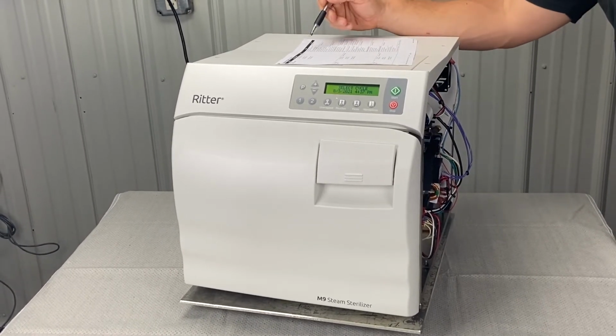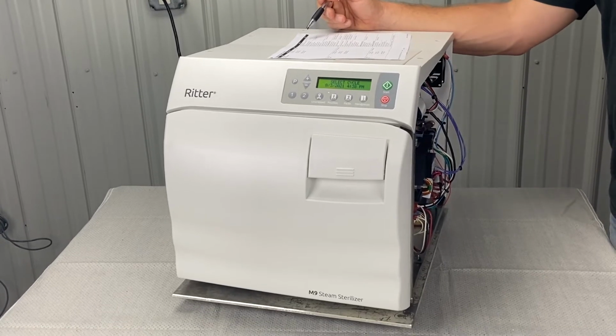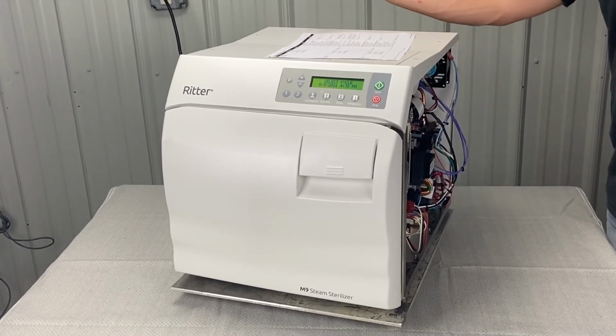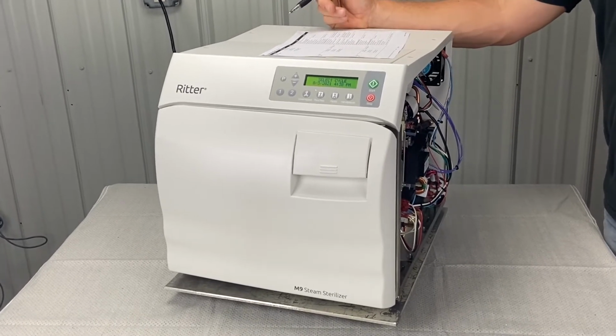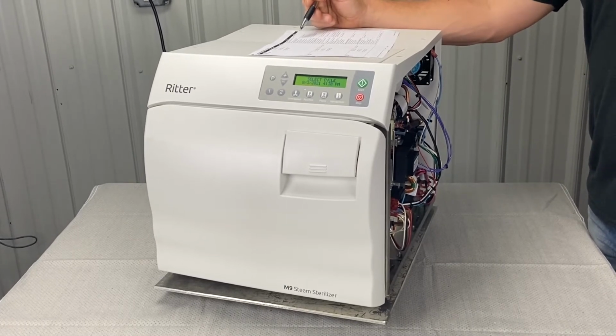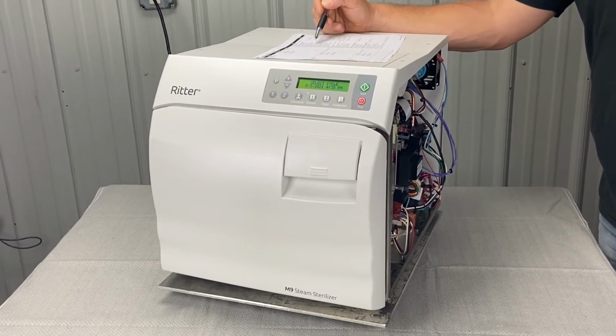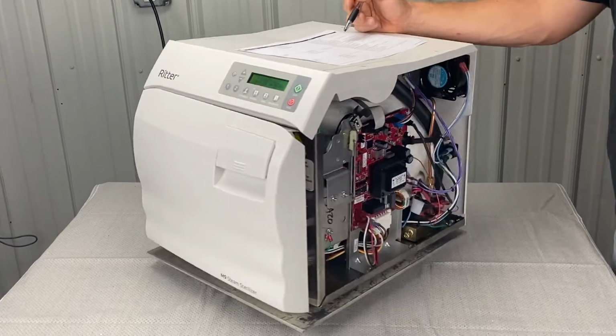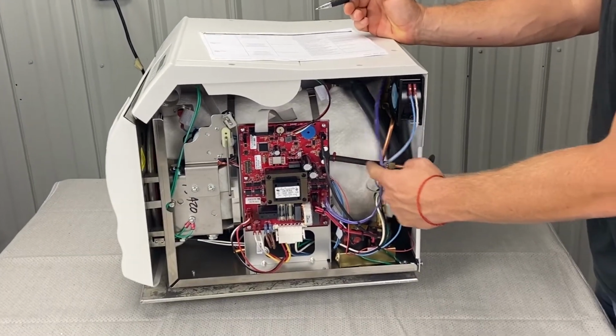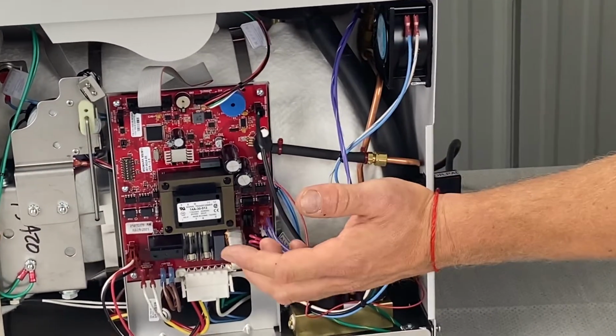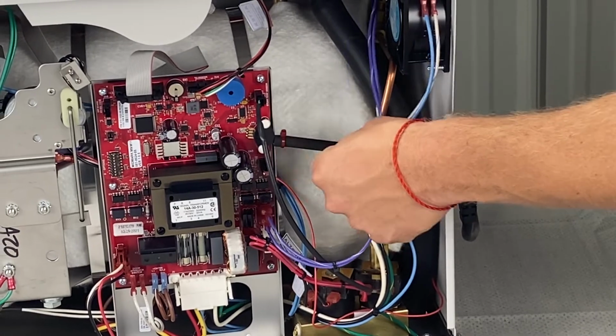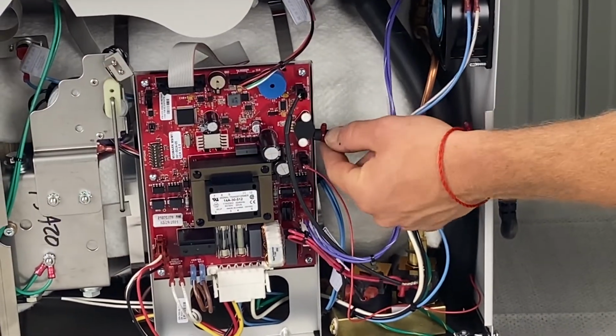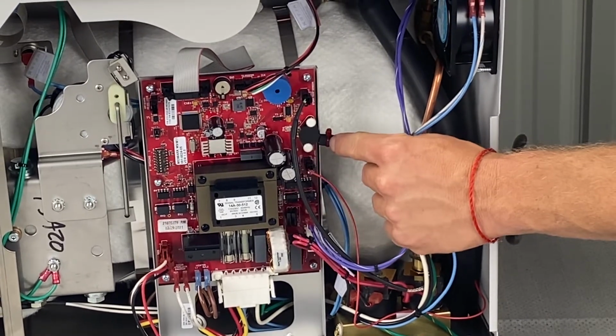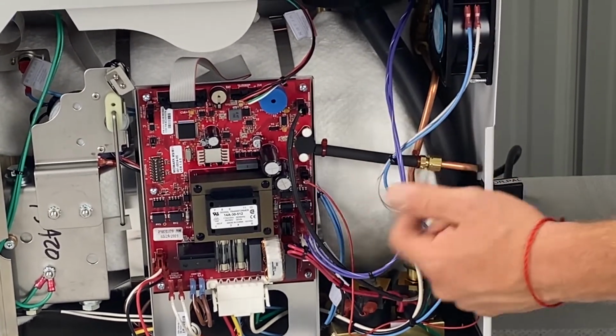Fill valve again, check for water leaking back into the reservoir through the fill line. So we're going to have to take the cover off to do that. If you want to do that, let's talk about it. Leaking or defective air valve, we talked about. Pressure transducer tubing. This is also an issue. It happens to us all the time when we're testing them. Maybe we forget to hook it up and it's just blowing steam out the side here. Or it's dripping, or if you don't tighten the zip ties, it could be leaking there.